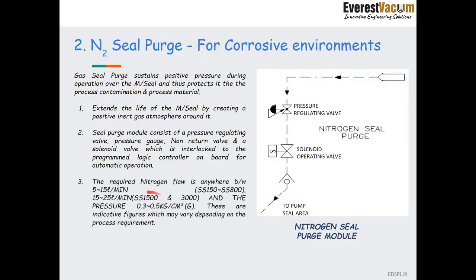Now the required flow is anywhere between 5 to 15 LPM for our 4 models, that is 150, 300, 400 and 800 meter cube per hour dry screw vacuum pumps. And the pressure required is 0.3 to 0.5 kg per centimeter square gauge. At plants, the pressure is much higher. That is why we have installed a pressure regulating valve over here.